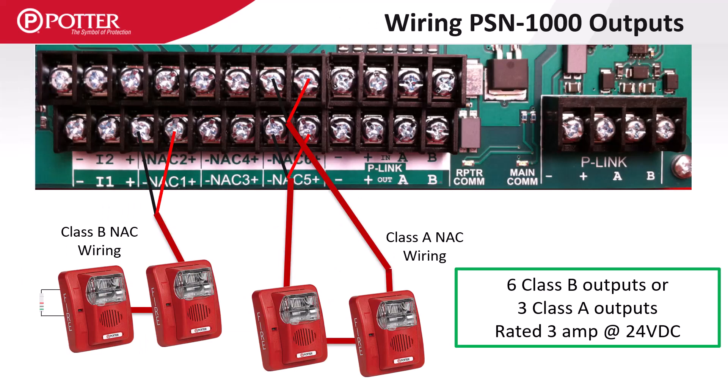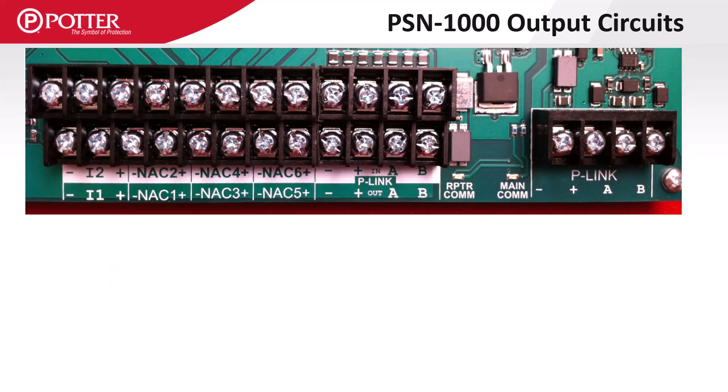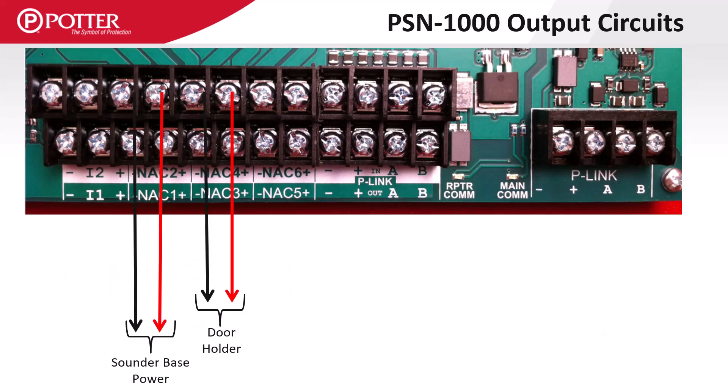The outputs on a PSN1000 have the same 3A circuit rating as a control panel. The power supply provides six Class B or three Class A outputs, which are independently configured using the programming software. Just like on the control panels, each output is independently configurable.